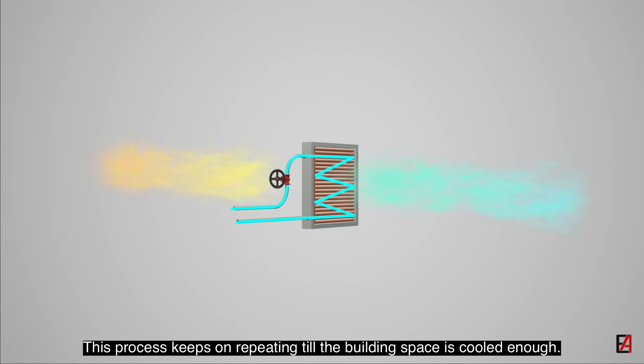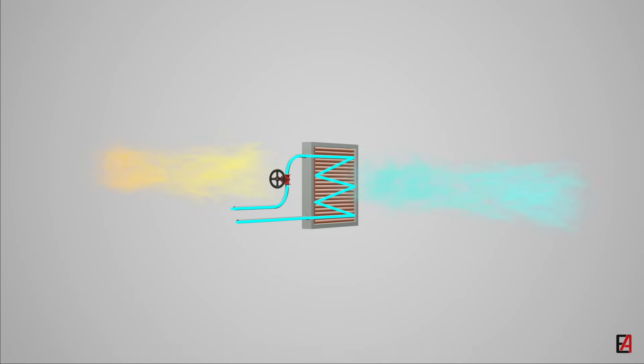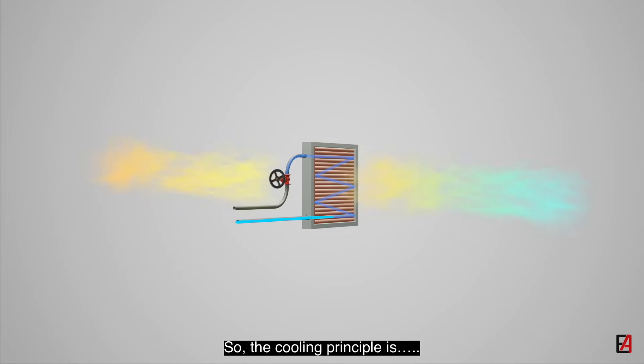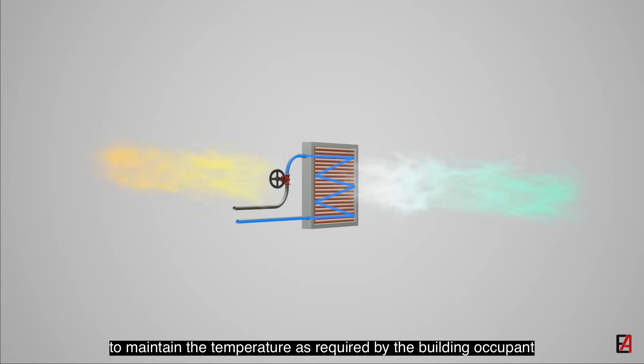This process keeps on repeating till the building space is cooled enough. At some point of time, the building space will be much colder and would require the valve on the cooling coil to be closed to maintain the desired temperature. So the cooling principle is, the cooling coil valve will be either opened or closed to maintain the temperature as required by the building occupants.